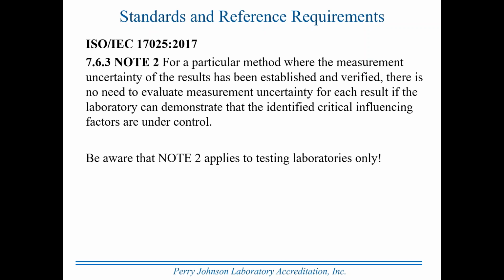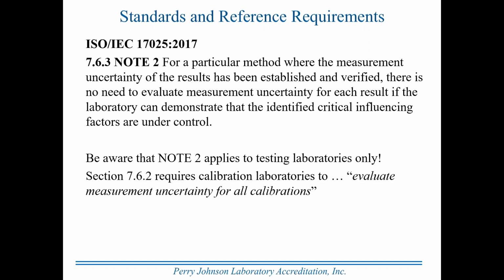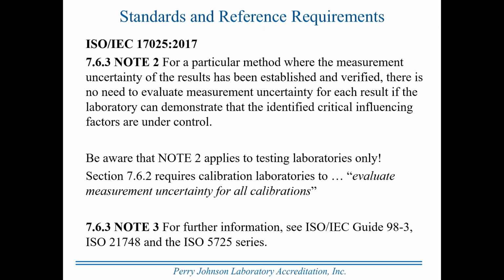Be aware that Note 2 applies to testing laboratories only, not calibration laboratories, testing labs only. 7.6.2 requires calibration laboratories to evaluate measurement uncertainty for all calibrations. 7.6.3, Note 3, gives you a source for additional information on this topic: Guide 98-3, ISO 21748, and the ISO 5725 series of documents.